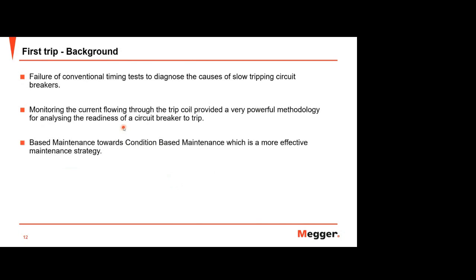And the background, why we have the first trip testing in the market now. Yeah, the failure of the conventional timing test to diagnose the cause of a slow tripping circuit breaker. This is the main reason that led to the search for a technique that will pinpoint the cause during the critical first trip. Although a timing test can confirm whether the circuit breaker's overall operation is within set limits or not, it was discovered that monitoring the current flowing through the trip coil provides a very powerful methodology for analyzing the circuit breaker trip.